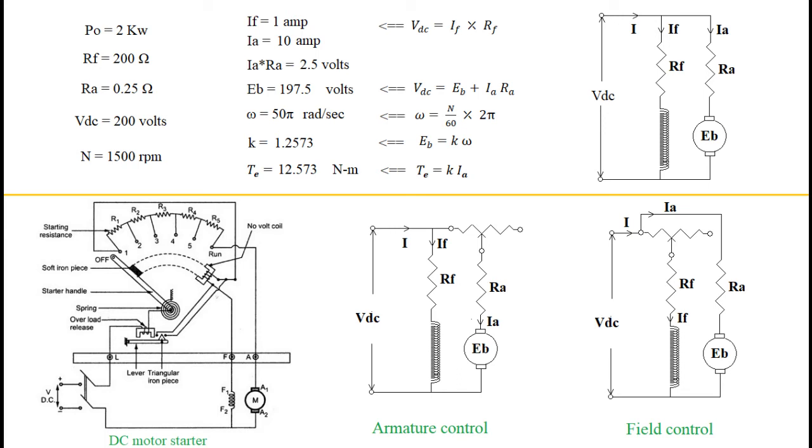Now let's consider armature control of the DC shunt motor. As shown in the slide, resistance is included in the armature circuit. This additional resistance reduces armature current and available torque. Since field circuit voltage remains constant, the magnetic field provided by the poles remains the same.